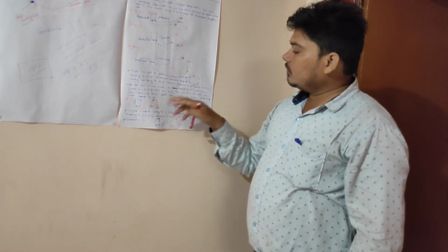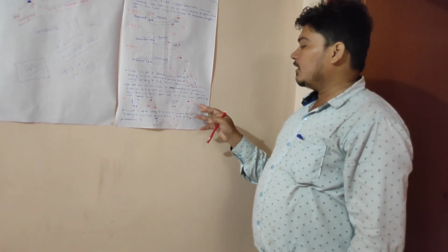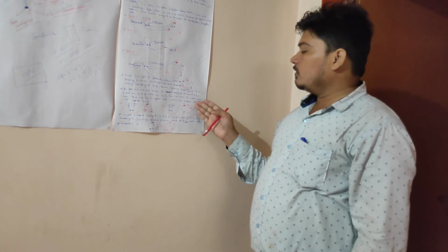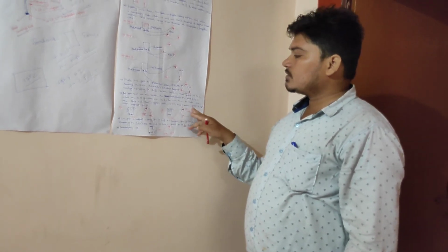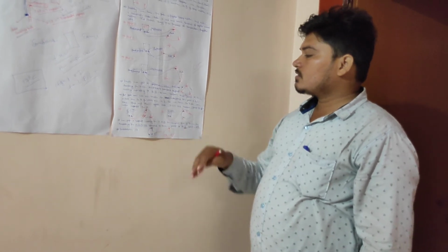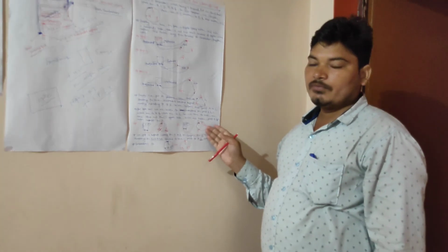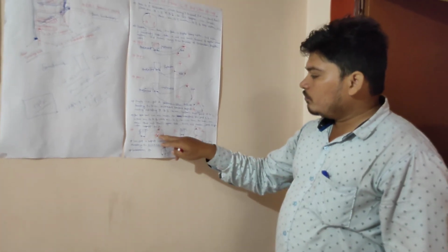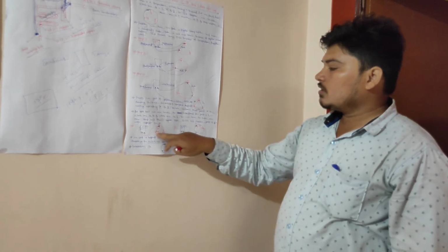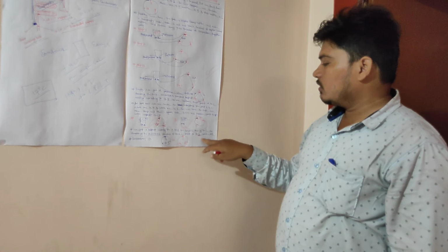So finally we get like this. Between A and B the reading value is 30 ohm, and between A and C the reading value is 17 ohm. 17 ohm between A and C resistance value, 30 ohm between A and B resistance value. So 30 is more than 17. So B point should be a starter and C point should be running.